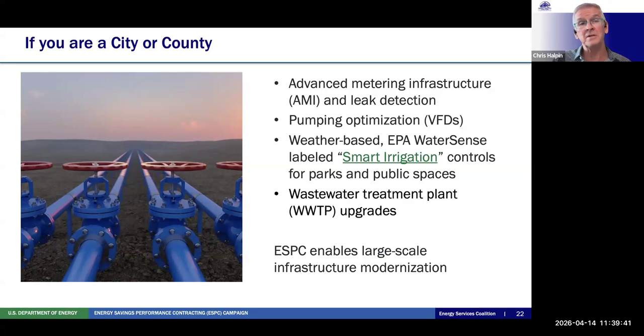Same with pumping optimization. Every water system and wastewater system in this country is designed for the peak day - you'll hear me talk about this later for Los Angeles County, 500 million gallons a day. That's what all the pumps, piping, and valve sizes are set for - that one worst day, and that's for the future day. These things get designed 30 years ahead of time, knowing there's going to be growth in the community. So sometimes these 1,000 horsepower motors - and I've stood next to these - are running at full speed, pumping a third of the water that's needed. And they end up putting pressure reducing valves after them, which just takes all the thrust out of those pumps and dissolves it.